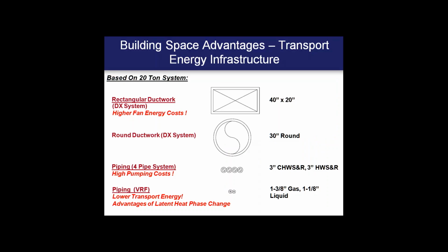Again, originally coming into the market, I think VRF had a niche application in more of the retrofit, historical renovation type projects, and that is because of the space saving advantages. But as I mentioned, it's extended into other areas of the commercial market and proves to be a viable option. But in terms of transport energy requirements, VRF is really one of the lower system choices, aside from the space savings advantage. So if you look at a centralized air handler, for instance, on a small 20-ton system, you're dealing roughly with a 40-inch by 20-inch ductwork. Again, you've got typically longer duct runs, higher external static pressure, and in return, higher fan energy costs. And consequently, historically, fan energy is probably one of the biggest contributors to energy consumption in commercial buildings.